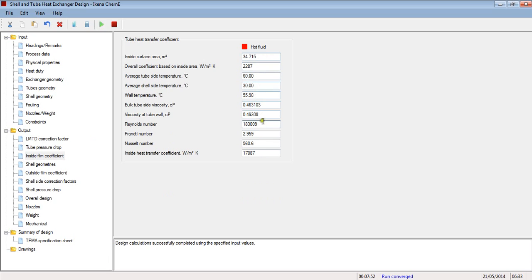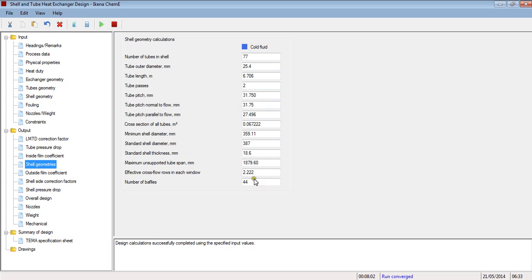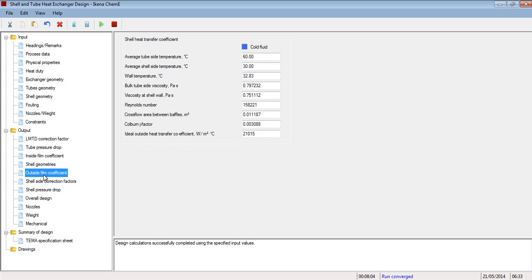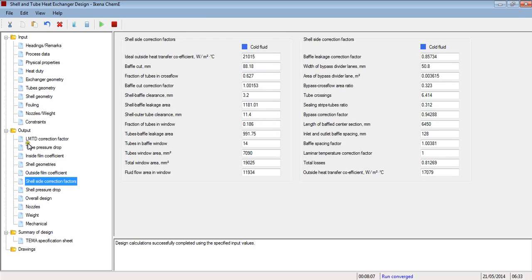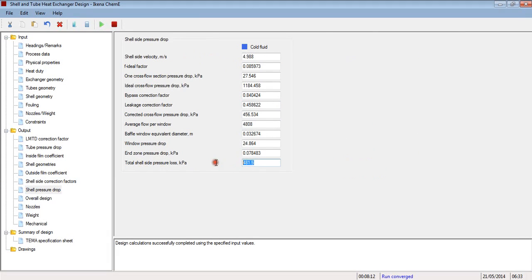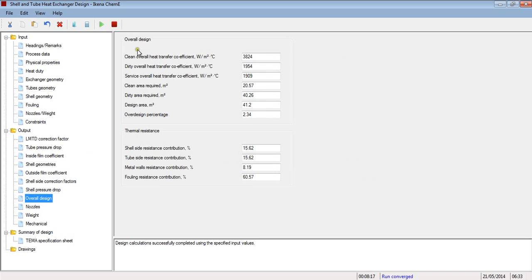Now here you can find information which is not in there, all of the output information. So you can just browse through this and look for the information that you're looking for. Shell geometries, there is some information in here. Heat transfer coefficient values here, shell side baffle cut values here, things like that. Shell side pressure drop is roughly 5 bar or 5 atmosphere, roughly. Over here you can get an overview of your design of your heat transfer coefficients. There's the clean, dirty, there's the service type, this 2.34 is the over design.